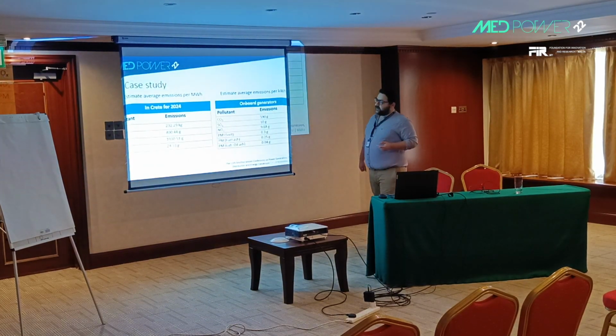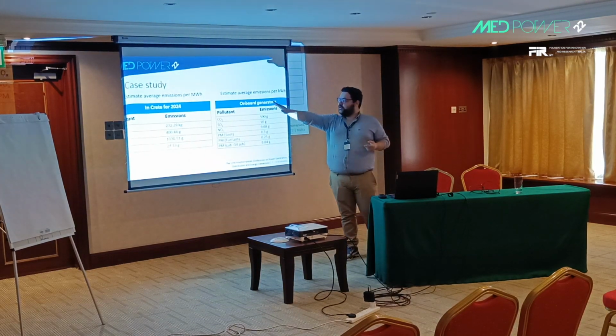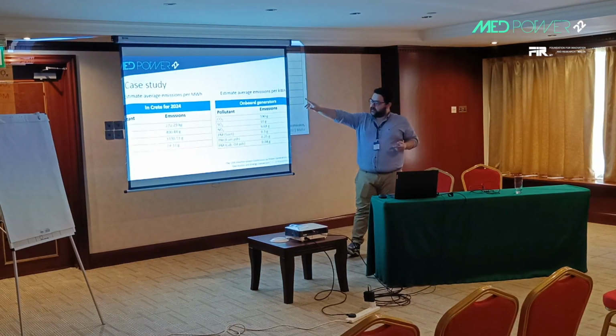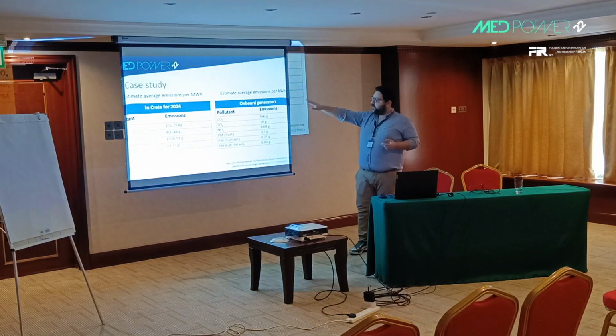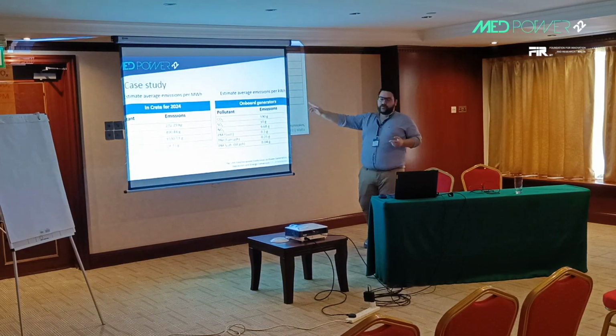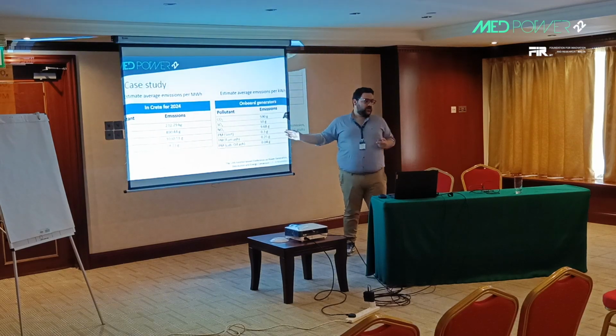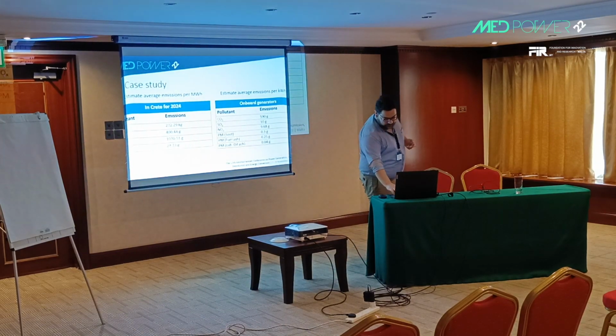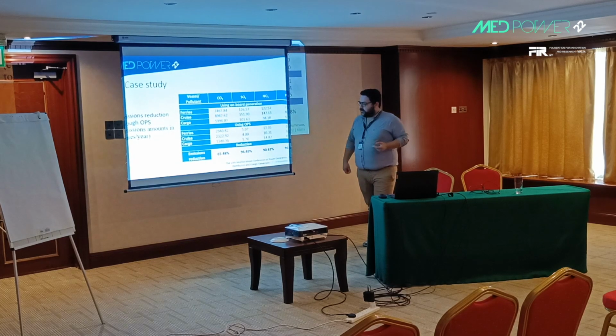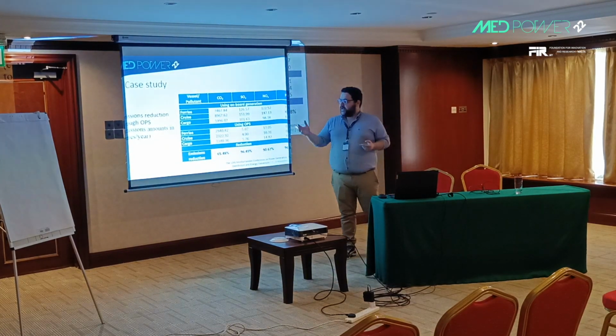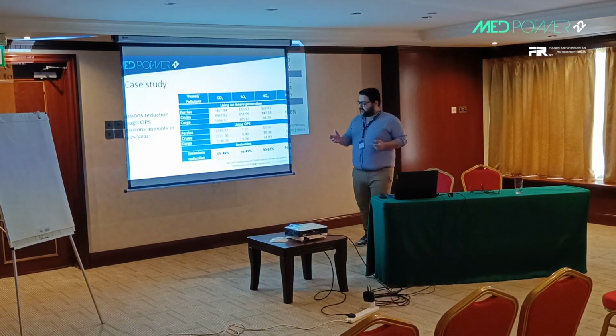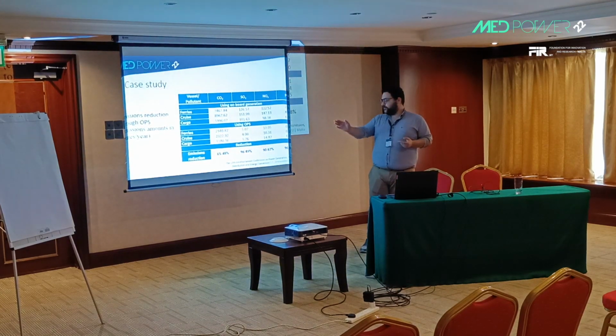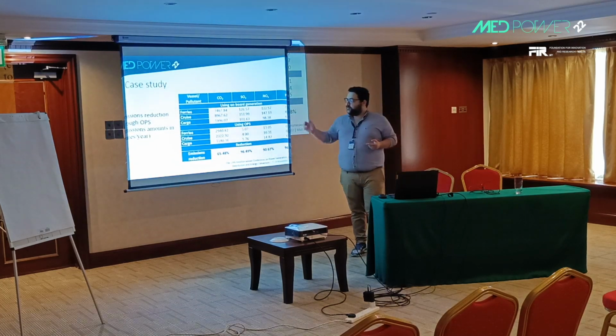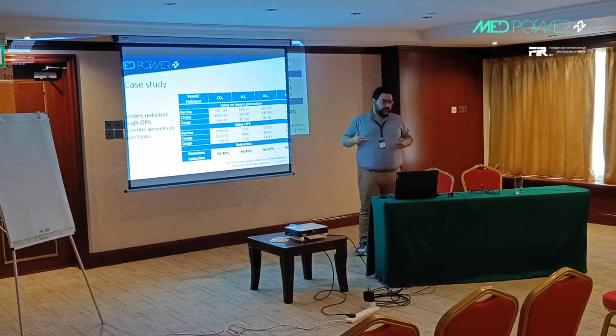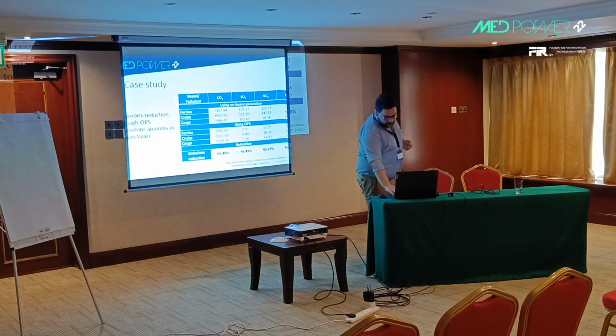This is an exemplary case of the average emissions per megawatt hour for the power system of the grid, and the estimated average emissions per kilowatt hour for the onboard generators of ships berthing at Heraklion. To simplify this, when we take into consideration OPS, onshore power supply, for all the ships, we can achieve an emissions reduction ranging from 65% up to 96%, according to each pollutant. So it becomes a very important problem to tackle.